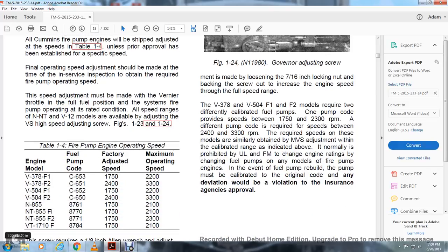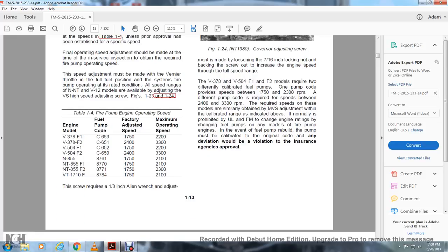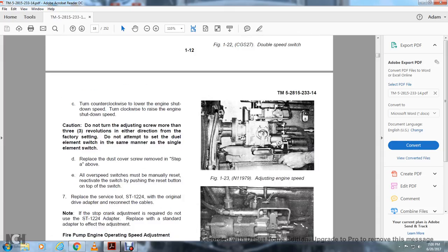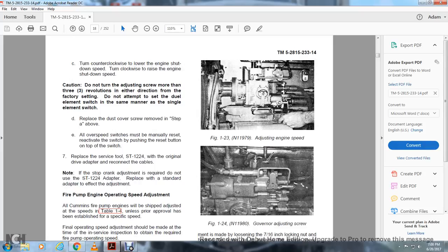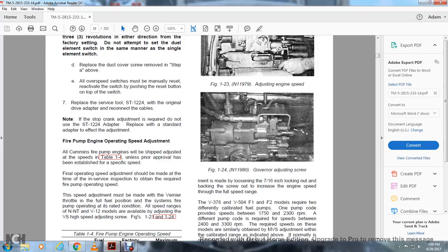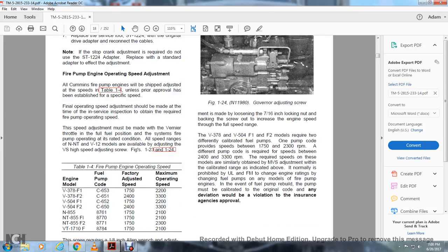Table 1.4 lists the fire pump engine operating speed: the engine model, fuel pump code, fuel factory adjusted speed, and the maximum operating speed. The screw requires a 1/8 inch Allen wrench for the adjuster, figure 1-23, adjusting engine speed, and figure 1-24, governor adjusting screw. The adjustment is made by loosening the 7/16 inch locking nut and backing the screw out to increase the engine speed through the full speed range for the V-378 and V-504.